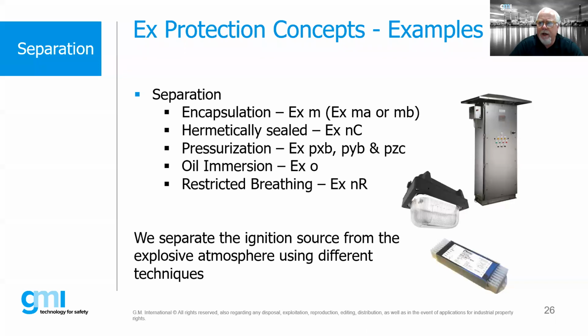Now, the other one is separation, and there are quite a few of these. The one that we most commonly look at is pressurization, which is EXP. The concept here is that we pressurize the inside of an enclosure to a level just above whatever the atmospheric pressure is, and we keep positive pressure so no gases, during normal heating and cooling during the day, will get onto the inside of the enclosure and potentially come into contact with any arcing or sparking devices. So it's a very effective means of protection. One of the drawbacks with EXP is that we typically need a source of good clean air, and this is not always available in certain facilities. But if we have instrument air, we have clean air that's there, and certainly it is a protection concept that can be used.